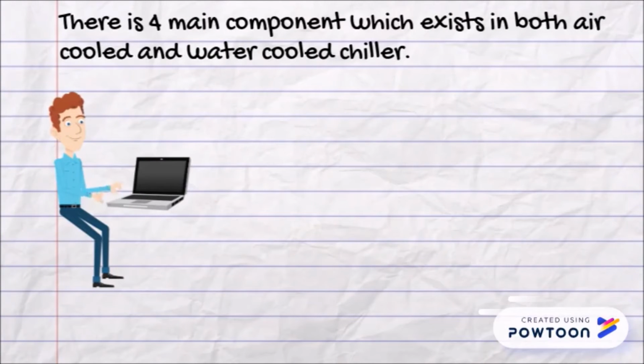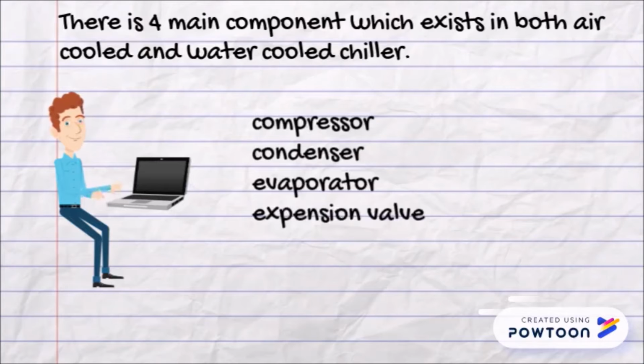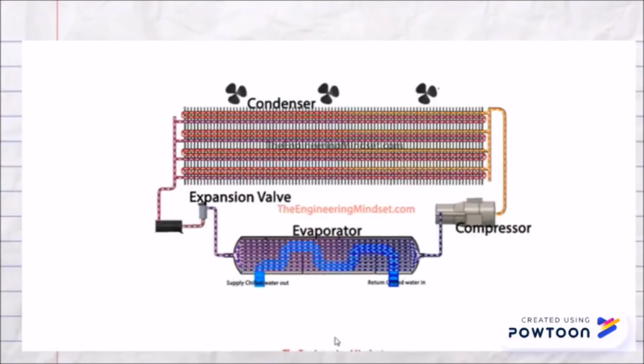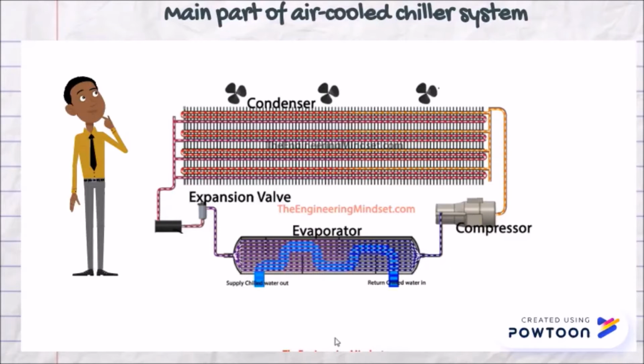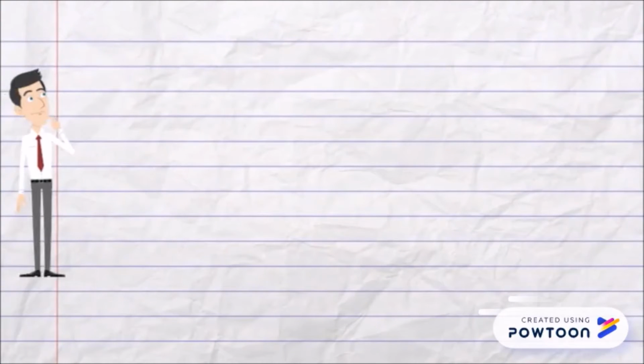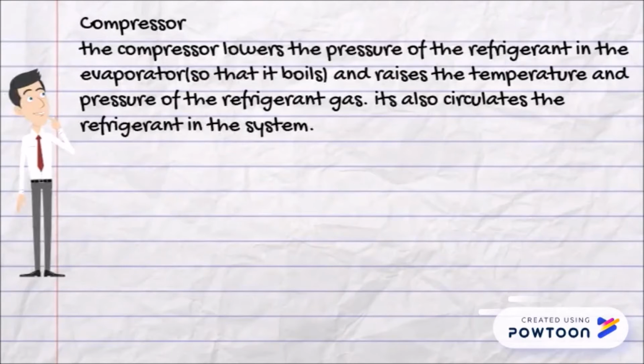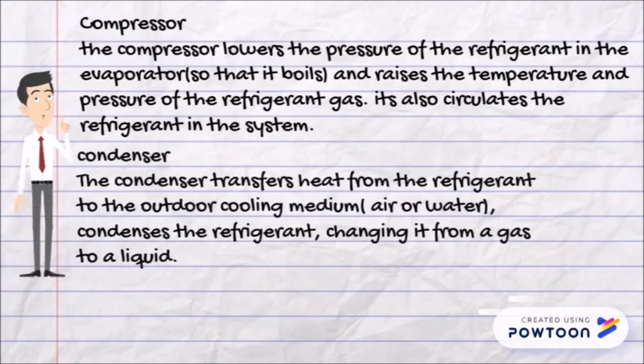There are four main components which exist in both air-cooled and water-cooled chillers: compressor, condenser, evaporator, expansion valve. This figure shows the main parts of the air-cooled chiller system. Compressor. The compressor lowers the pressure of the refrigerant in the evaporator so that it boils, and raises the temperature and pressure of the refrigerant gas. It also circulates the refrigerant in the system.